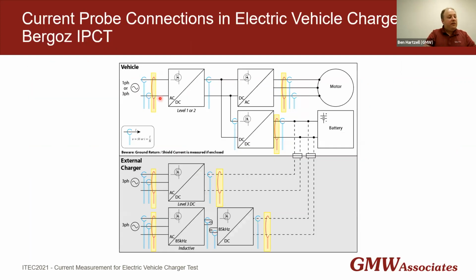And so here you see the connection points. They're going to be anywhere we would want to make that differential measurement in order to look for any sort of leakage or loss. So any multi-phase measurement, or again, the positive and negative here on the battery for the DC battery charging currents.